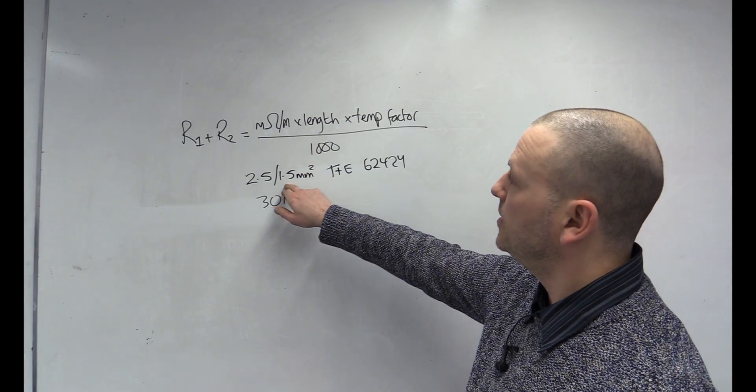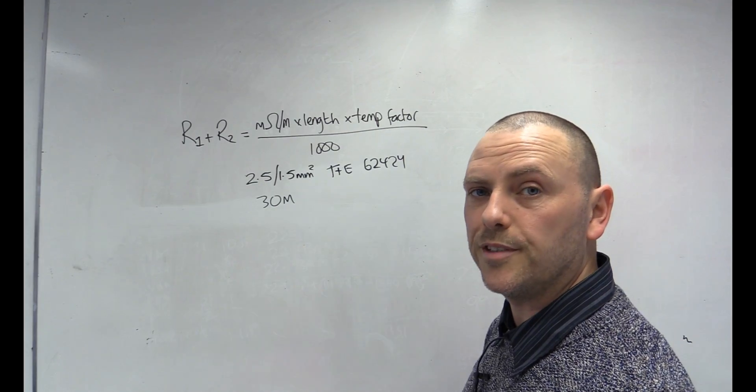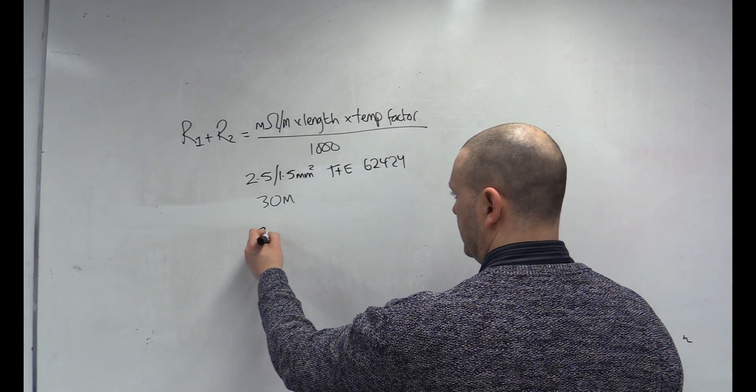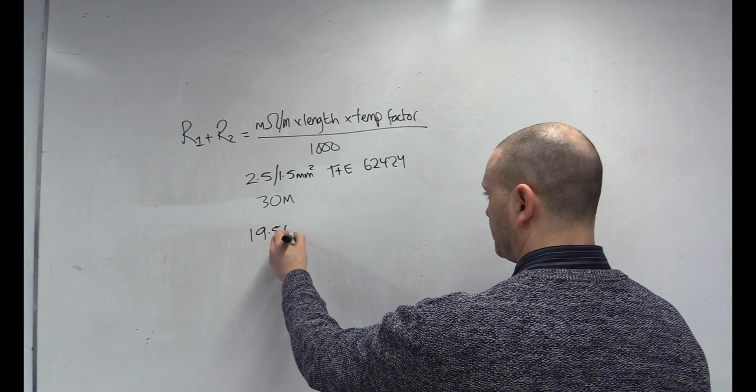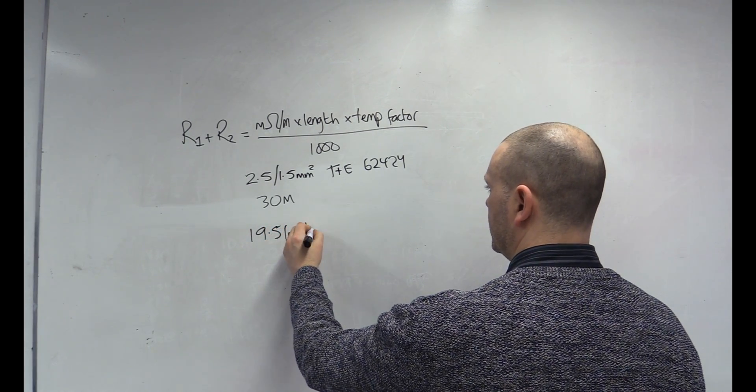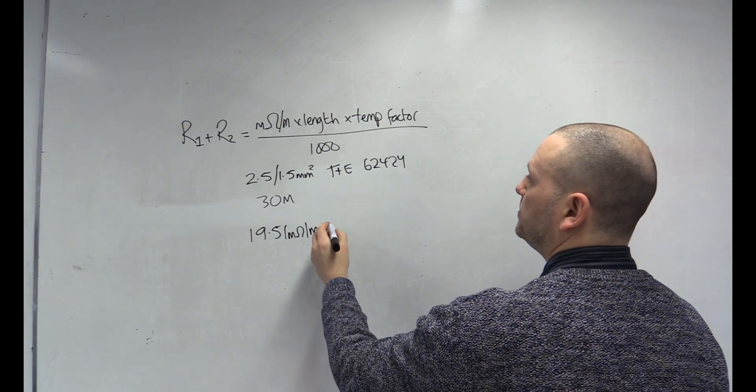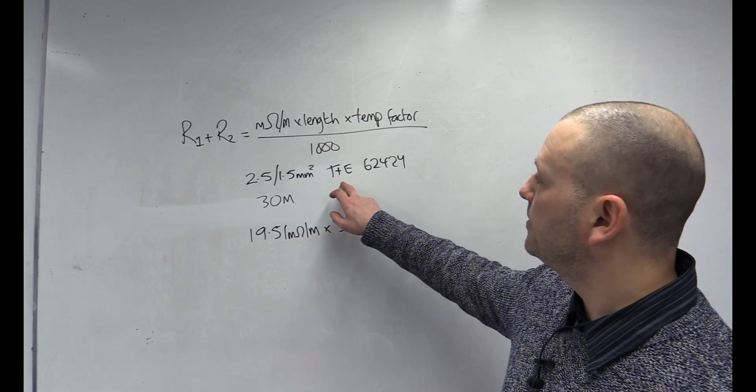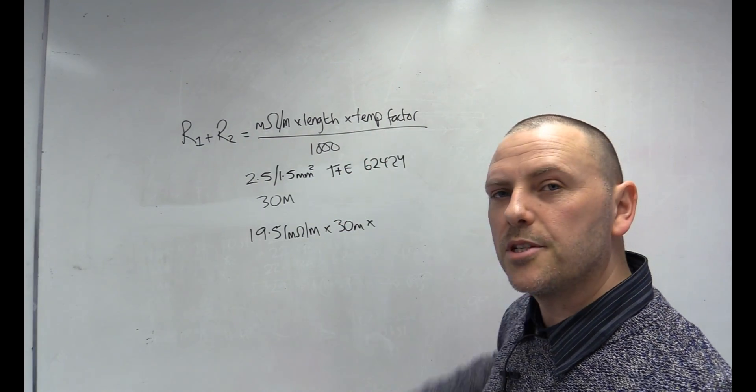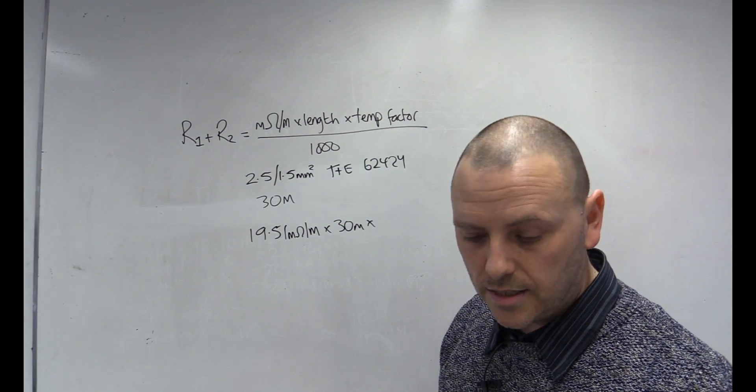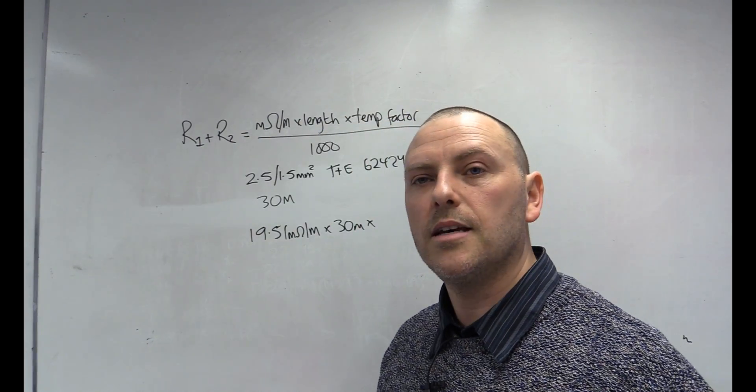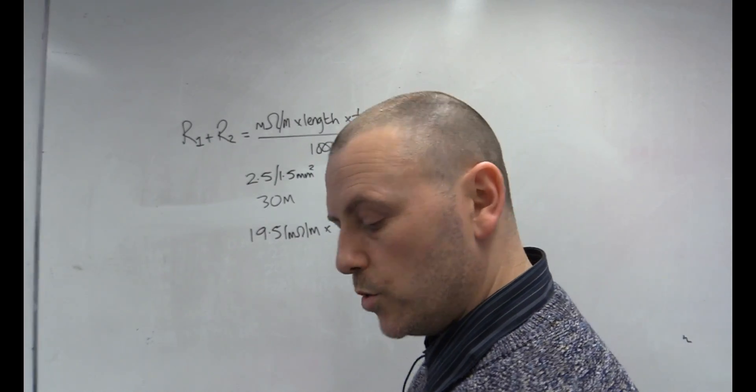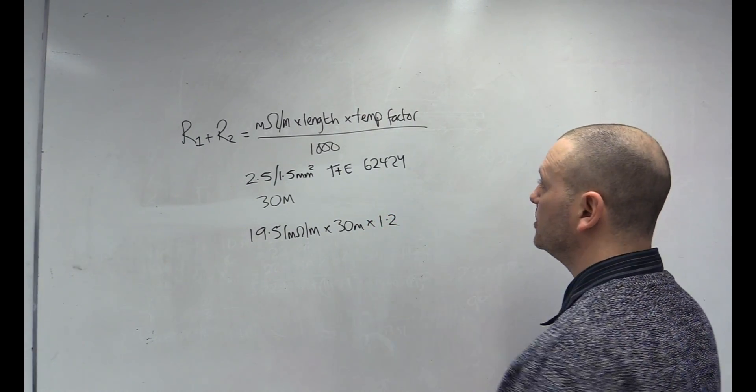First off, we just need to find out what the milliohms per metre value is for a 2.5, 1.5 cable. And when you have a look in that table, you'll see that it's 19.51 milliohms per metre. We times that by the length, 30 metres. Now, a twin and earth is a 70 degree cable. So, we need the temperature factor for a 70 degree cable. And when we have a look at table I3, we will see that it's 1.2.